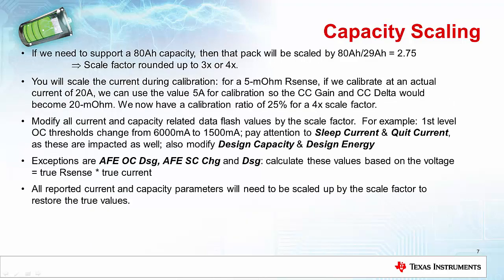And capacity scaling is the other area where we run into customers who have much larger packs than what we may be able to handle natively in the firmware. Most of our gauges can handle up to about 29 amp hour for these multi-cell gauges, but we have many customers using much larger size packs than that. So for example, if you had an 80 amp hour pack and we can only support 29 amp hours, then you need a scale factor somewhere in excess of 2.75, so maybe 3x or 4x. And this approach is basically the same thing as we used for current scaling earlier.